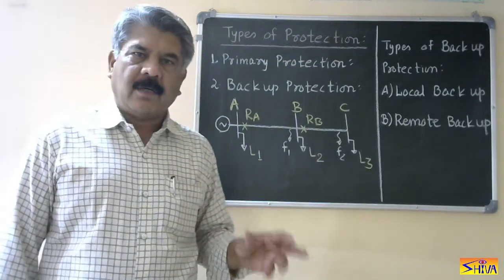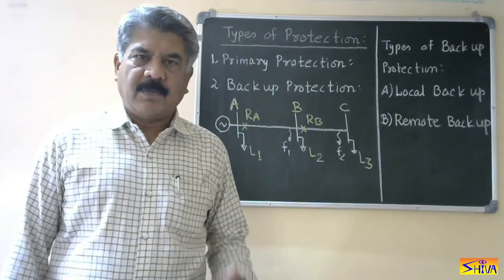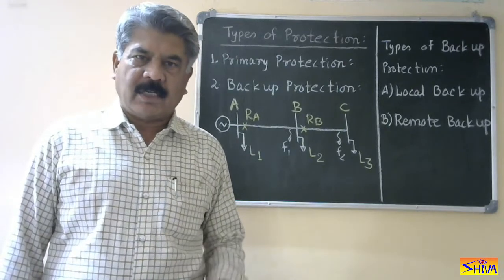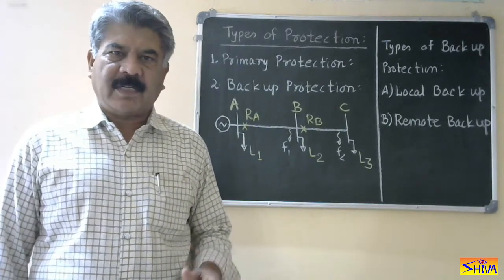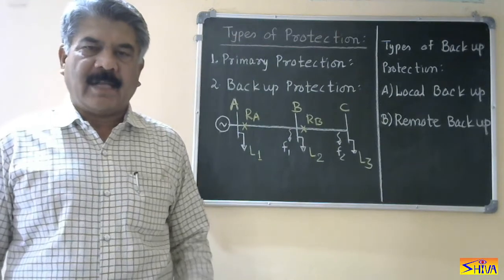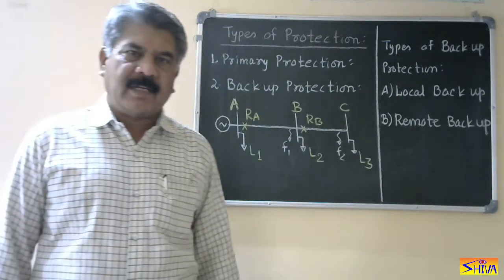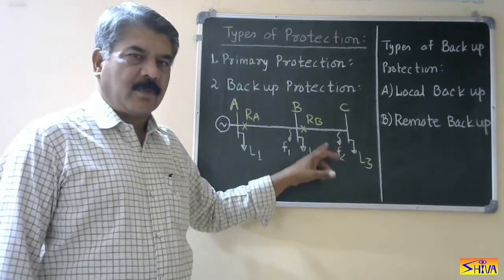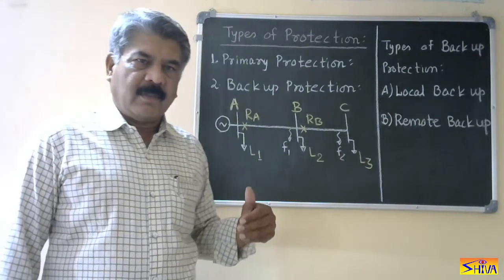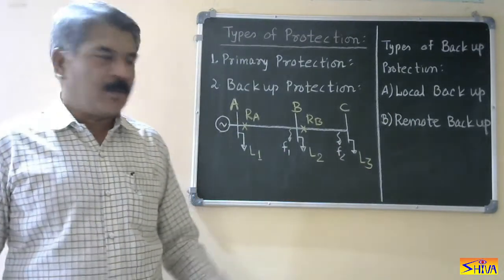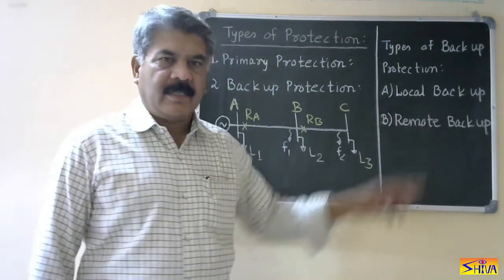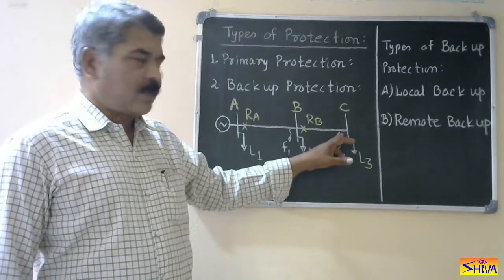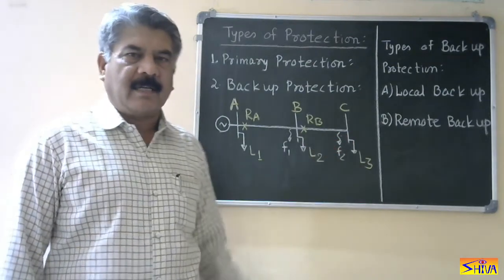The drawback of local backup is that it requires additional cost. If we duplicate the entire protection system, we provide two relays, two circuit breakers, two trip coils, two trip circuits, two DC power supplies, and so on — so the cost is more. But the advantage is that it operates in the same least possible time. If the primary protection fails, the local backup protection operates in the same time, and only the faulted portion is disconnected from the system.